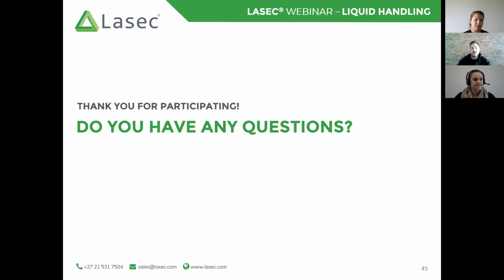But if you were trying to verify this or calibrate it according to the standard, or check it against a previous calibration, you would need to repeat exactly what they have carried out, in which case if they've used distilled or deionized water, it is imperative that you do the same. However, if your question is, if we are verifying or adjusting our pipette for the use of this liquid, can we use it to calibrate? You can. But with organic solvents, I think you might struggle to get that accuracy, precision, and essentially the repeatability out of those results, just because of the properties of that sample.